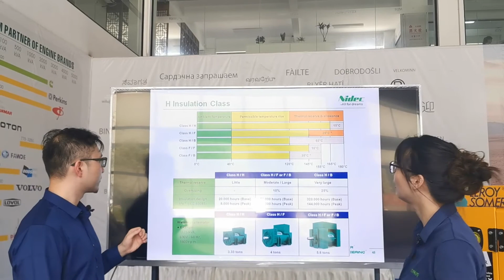With H insulation class, H is the highest one. No matter what temperature rise class it's combined with — H level, F level, B level — we can make sure the life of the insulation is the longest. H insulation class offers the highest temperature rise buffer for all applications, so H class is much better than lower ones like F or B.